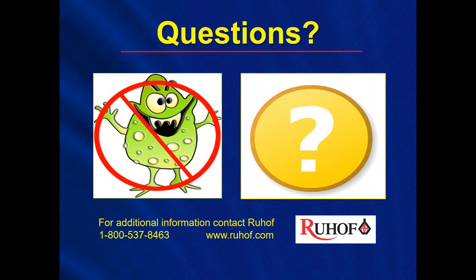With regards to when the ATP testing should occur, I did hear of a hospital that was doing ATP testing after bedside cleaning, manual cleaning, and high-level disinfection. The problem with that is if you're testing a scope that's supposedly ready for patient use, you are now contaminating it by doing the ATP test, and then you would have to reprocess it all over again.